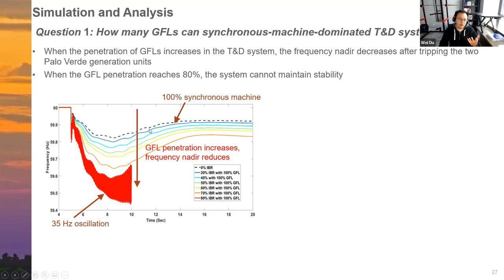The base case with zero inverters is the black dashed line, and the system primary frequency response is like this. But if we keep increasing the penetration of grid following inverters, the frequency nadir is gradually reduced. When the penetration level of grid following inverters goes up to about 80%, the system cannot be stable, because we see some 35 Hertz oscillation. So for this platform, at least, it shows that when the penetration of grid following inverters goes above 80%, the system cannot be stable.